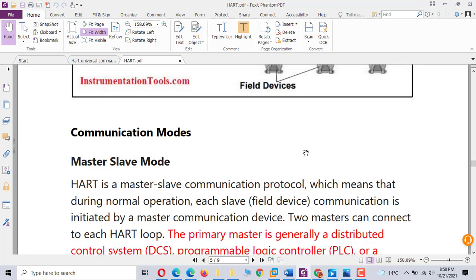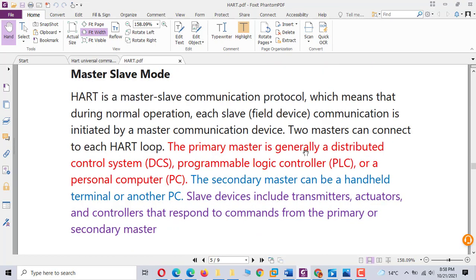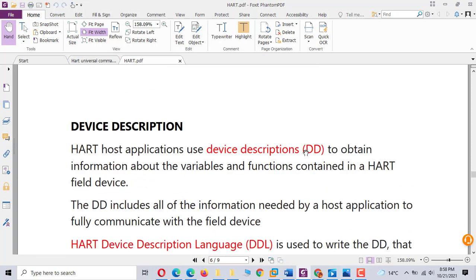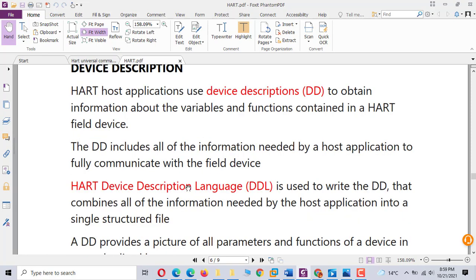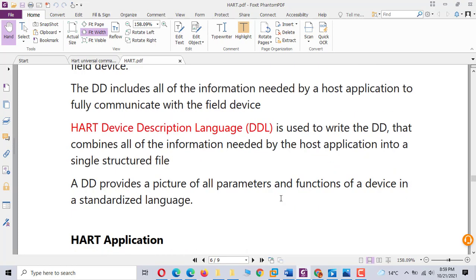The communication model is the master-slave model. For HART communication, all information uses a device description, the DD file. The DD file uses the device description language to write down everything. So sometimes if you use some HART device, you have to upload the DD file.